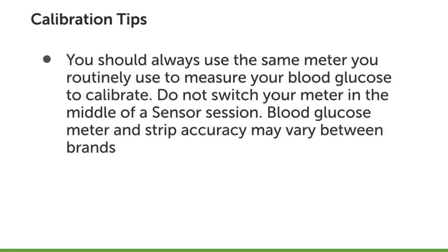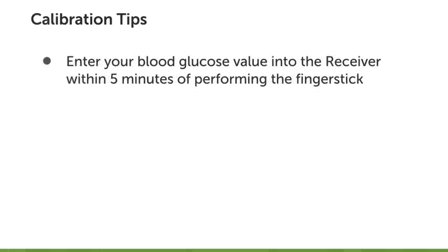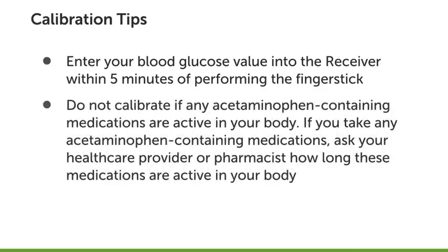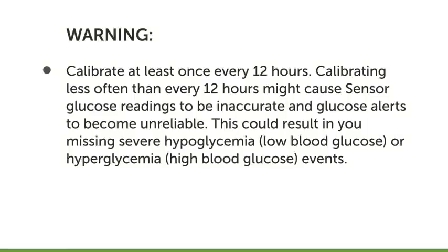You should always use the same meter you routinely use to measure your blood glucose to calibrate. Do not switch your meter in the middle of a sensor session. Blood glucose meter and strip accuracy may vary between brands. Enter your blood glucose value into the receiver within 5 minutes of performing the fingerstick. Do not calibrate if any acetaminophen-containing medications are active in your body. If you take any acetaminophen-containing medications, ask your healthcare provider or pharmacist how long these medications are active in your body. Warning: your sensor readings may be inaccurate if you calibrate less often than recommended.